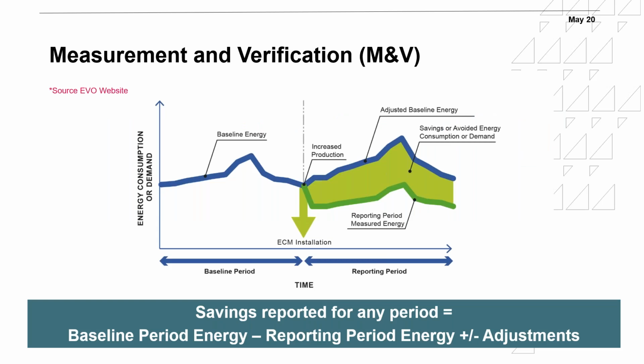You can see that this is the baseline energy here. So let's say this is the 2018 period. Okay, we implemented some energy conservation measures at this point. And here you can see there's a drop in the energy consumption due to these efficiency measures. And theoretically, these would be the savings here. However, let's say 2019 was a little bit hotter than 2018. So we need to adjust the baseline, meaning that we're going to say what would have happened to the consumption during 2018 if the temperatures were a bit higher outside. And that is what we call the adjusted baseline.